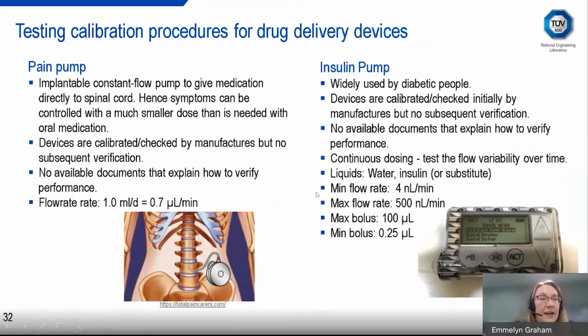Another device that we're going to test is a pain pump, and this is an implantable constant flow pump which is used to give medication directly to the spinal cord, and hence the conditions can then be controlled with a much smaller dose than what you would need if you were taking medication orally. Again, devices are checked and calibrated by manufacturers, but there's no subsequent verification, and there's no documents available that explain how you would verify the performance and do calibration checks. And you can see that we're going down to very, very low flow rates for this device.